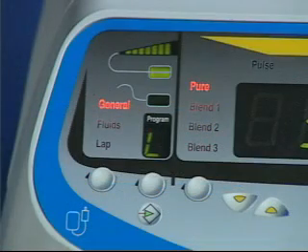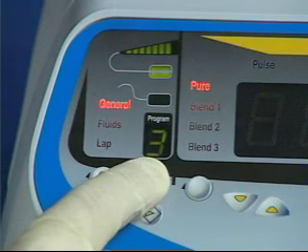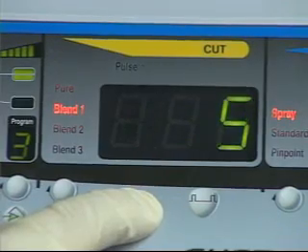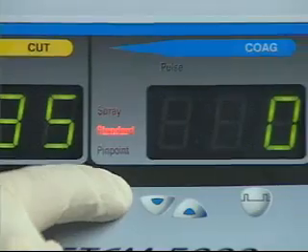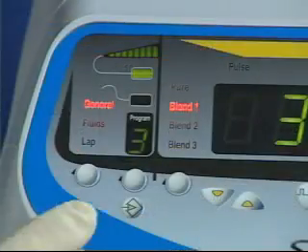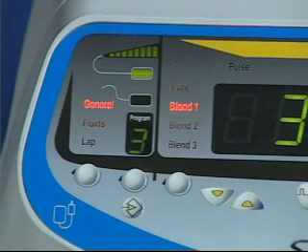To store a particular power setting, simply press the scroll button underneath the program display window to the desired location, enter the power and mode settings, and then press the store key. The system will acknowledge acceptance of the settings with two confirmation beeps. These settings will be ready for retrieval whenever that location is displayed in the program window.